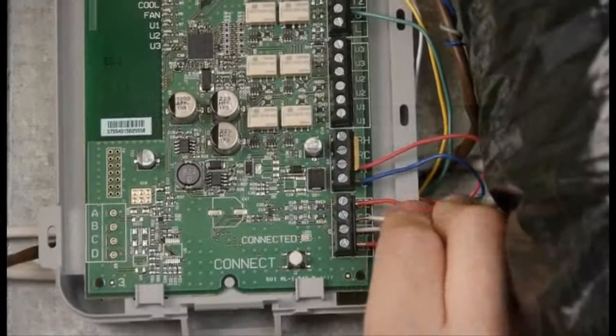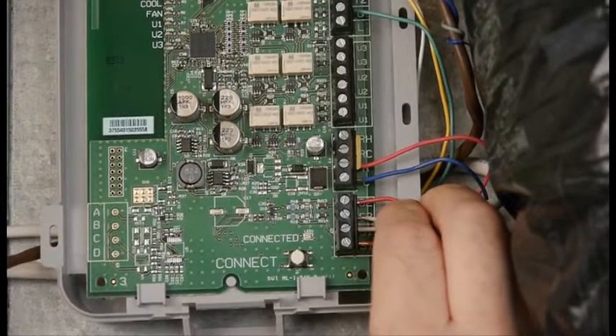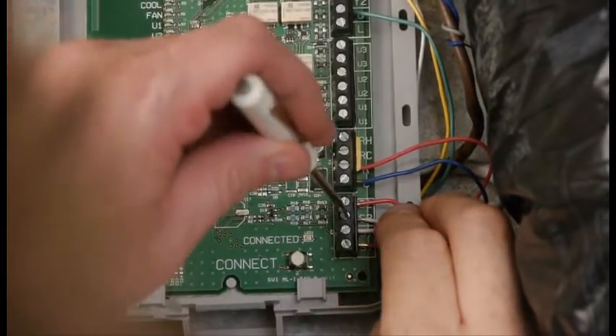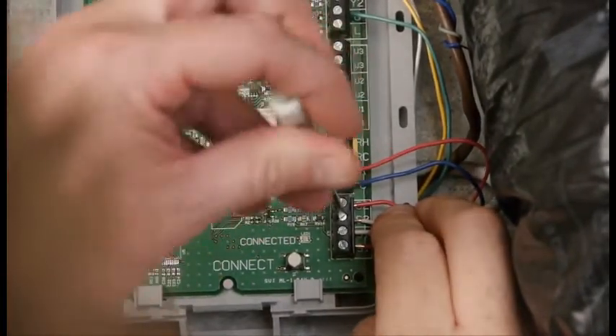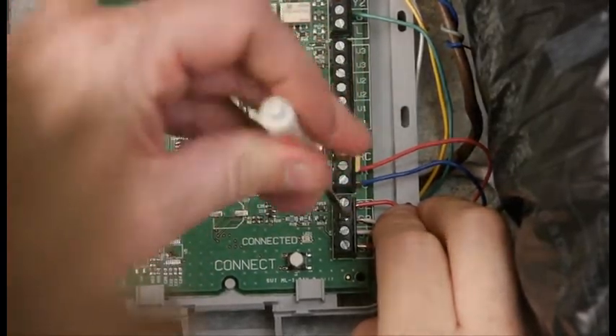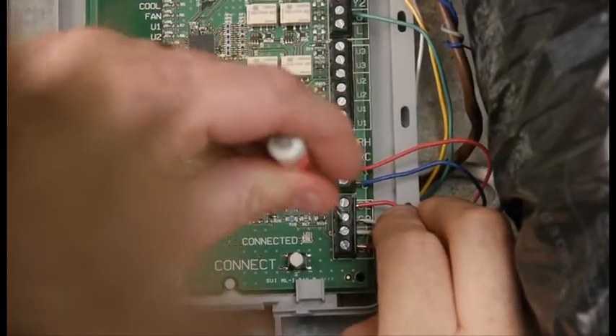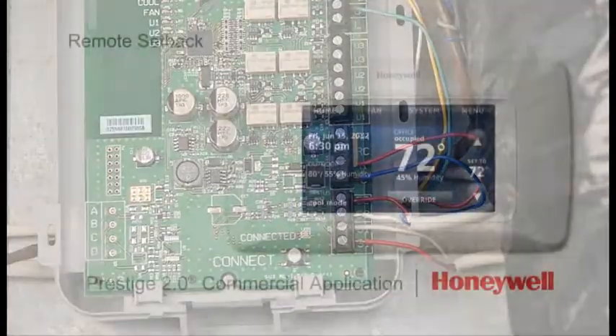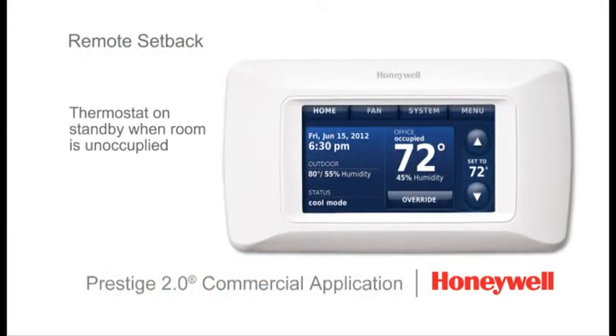When an occupancy sensor switch is connected to the S1 or S2 terminals at the Equipment Interface module, Prestige 2.0 lets you do a remote setback. A remote setback is the sensor telling the thermostat to go into standby when nobody is in the room. If someone is in the room, then it follows the settings of the occupied period.